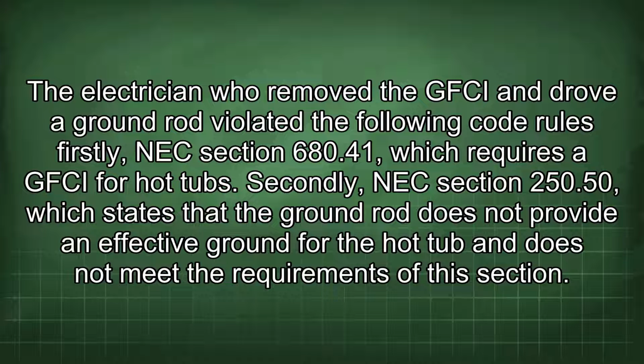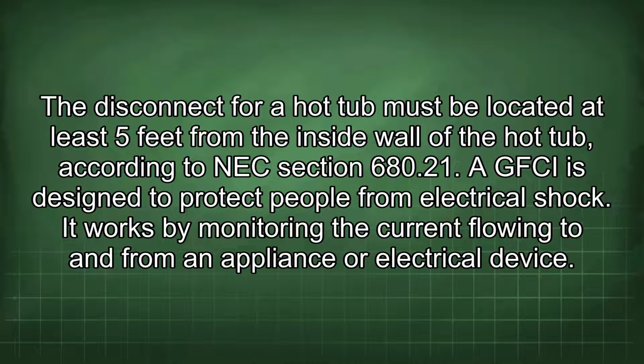Firstly, NEC Section 680.41, which requires a GFCI for hot tubs. Secondly, NEC Section 250.50, which states that the ground rod does not provide an effective ground for the hot tub and does not meet the requirements of this section. The disconnect for a hot tub must be located at least 5 feet from the inside wall of the hot tub, according to NEC Section 680.21.